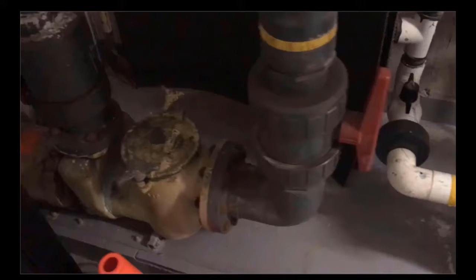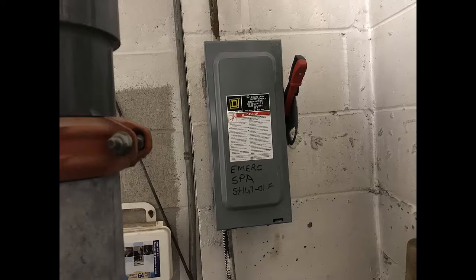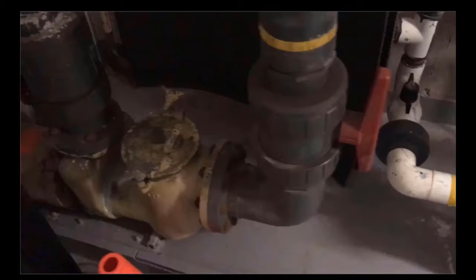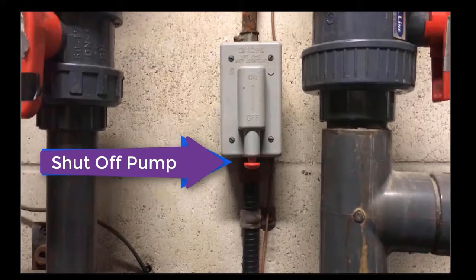So there's a couple of things I wanted to mention about the jet pump. One of the things I'll be doing in the next couple of days is cleaning up a little bit of the calcium buildup on here, wire brushing it down and getting as much cleaned off as I can. And to the left of that, on the wall, there's a large breaker that actually turns that jet pump off too as well. And that should be off if you're ever doing any work on the spa, like draining it or cleaning it or anything like that, as well as the main filter recirculation pump, and I'll show you where that is as well.